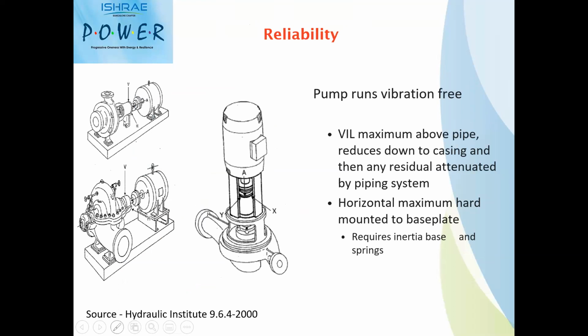In terms of reliability, as I told, vertical inline pumps have very less parts compared to your end suction or horizontal split case pumps, which has higher life compared to conventional pumping systems. This has been published also in the Hydraulic Institute standard, where they recommend people to go with vertical inline. So as I told, it all depends on project to project, wherein we select the pumps based on all the criteria in terms of performance, where you need to have better efficiency pumps, you need to have trouble-free operation pumps, you need to have ease of installation, you need to have low maintenance pumps, and more reliable pumps.